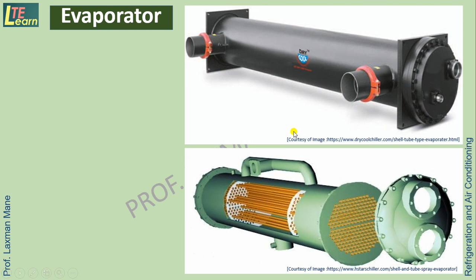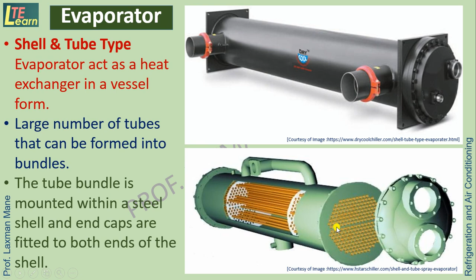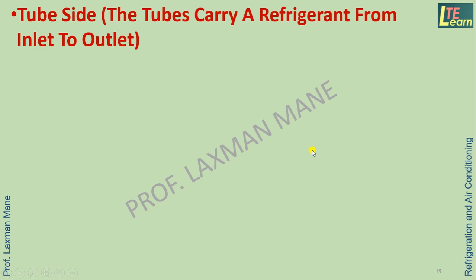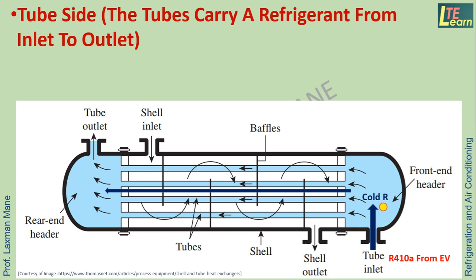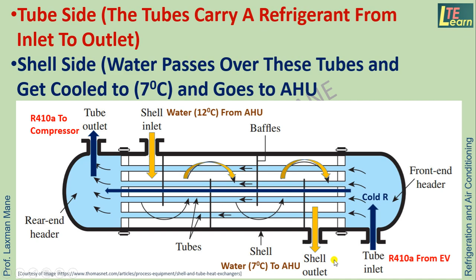In a vessel, a large number of tubes are formed into bundles. The tube bundle is mounted within a steel shell and end caps are fitted to both ends of the shell. So here, tubes carry the refrigerant from the inlet to the outlet, which is coming from the expansion valve. R410A is a cold refrigerant. When it is passing along the tube, it comes in contact with water on the shell side, which is coming from the air handling unit. So this water is getting cooled by the refrigerant, and this chilled water is passing to the air handling unit.